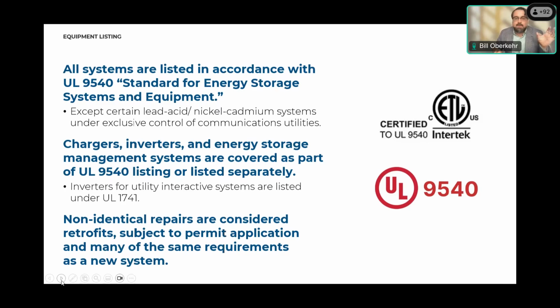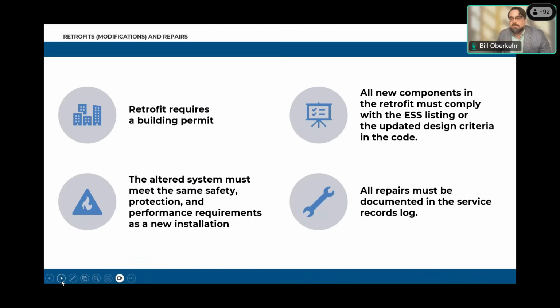Again, the UL 9540 equipment listing is required by code. The UL 9540 field listing is not a suitable replacement for the equipment listing. Next slide, please, to get a little more into some of those details.